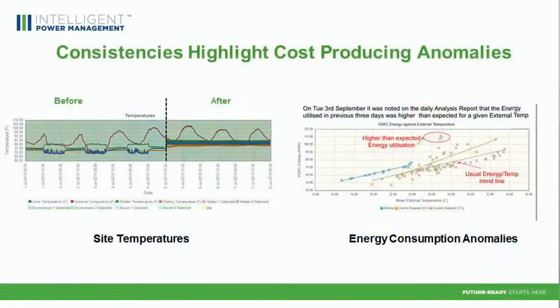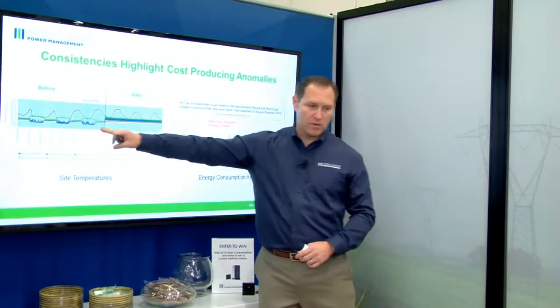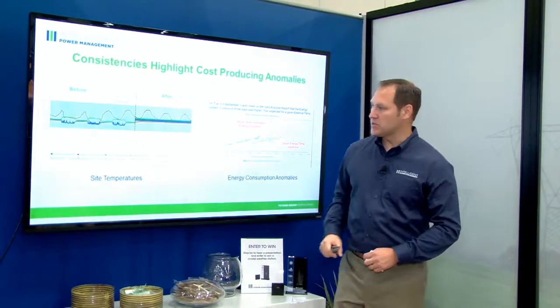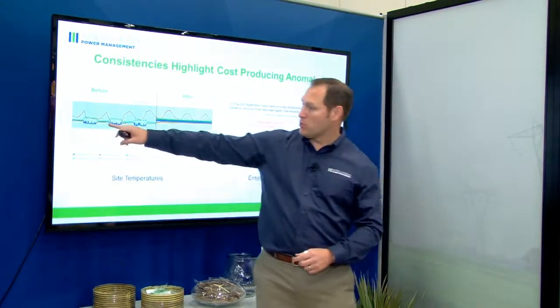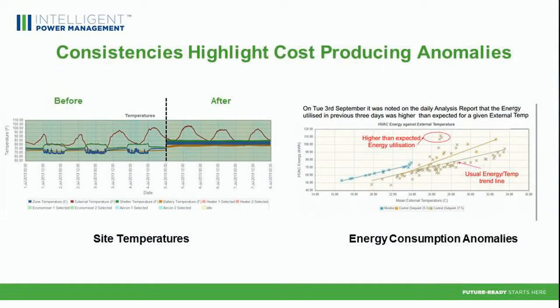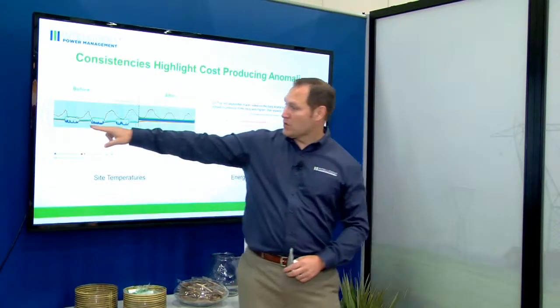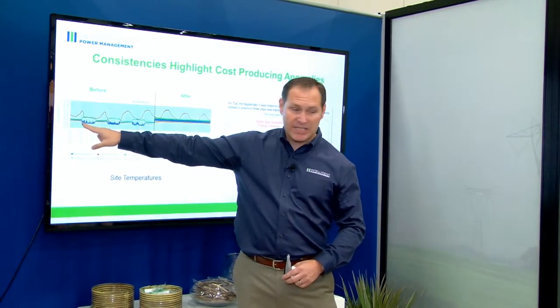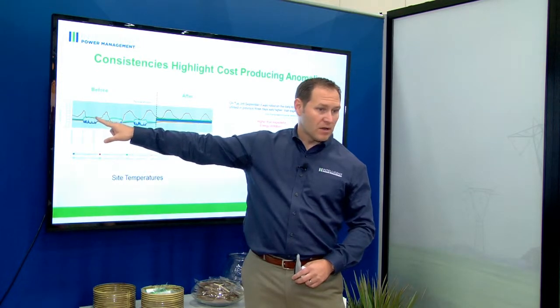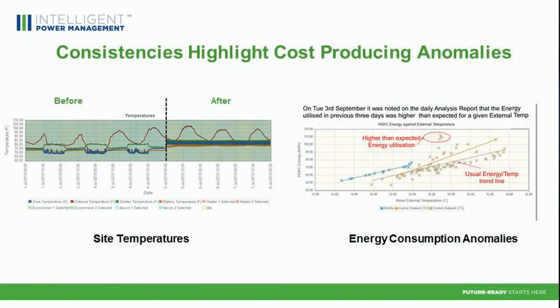This is a particular site of one of the customers we monitor today. This is site temperature before and after we install the IPM solution. You can see the red is outdoor temperature; the blue, green, and orange are different temperature set points in this particular site. For a block of about 12 hours a day — in this case from noon until midnight — there's a 10-degree difference in temperature between the two temperature set points in this shelter. The next day it does the same thing, and the next day it does the same thing.